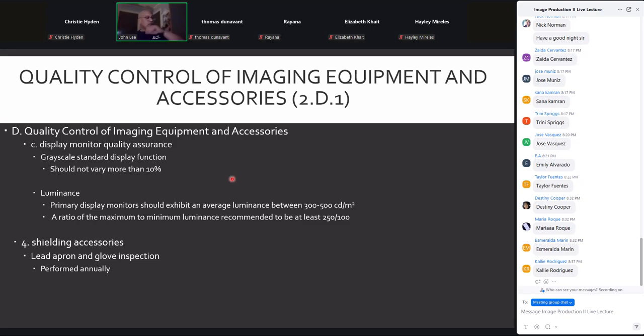The NCRP recommends a visual inspection annually. Visually, lay it out flat. Look at the cover. Check for frays. If it is frayed, see if it affects the lead or the integrity of the lead-impregnated vinyl. Then have it laid out flat. You're going to use your hands and tactilely inspect. Rub all of the areas of the lead, feeling for creases, divots, possible holes. If you do not locate any, the apron is good to go.